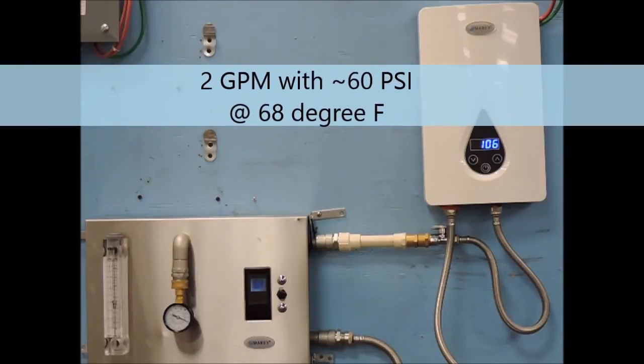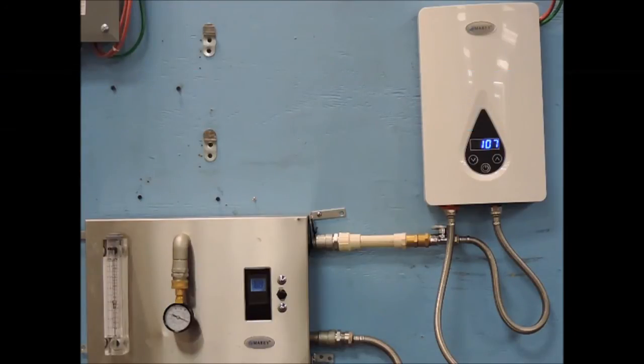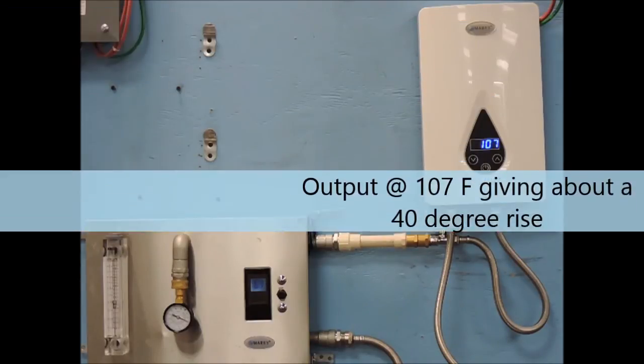On our second test, we have a flow rate of 2 gallons per minute, with 60 psi, and an incoming water temperature of around 69 degrees. As you can see with these inputs, we are receiving about 40 degrees rise in temperature.